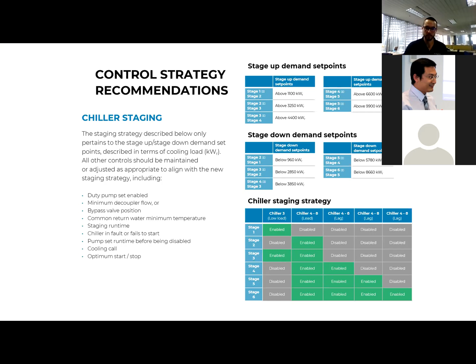And we can go into a few reasons why, but that's what causes that hump of savings at around the 3 megawatts of cooling range, is to bring this low load chiller back on. And actually the model liked the low load chiller so much that it tried to continually bring it back on for the entirety, which I can show you on this next slide.